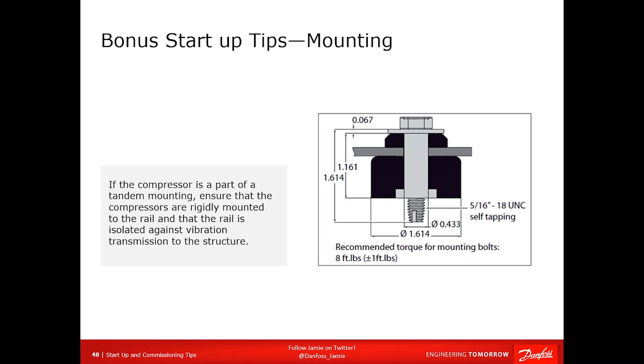This absolutely means these compressors cannot move independently. They have to move together. So do not float the compressors. Firmly attach the compressors to the rail, then float the rail on these rubber grommets to reduce vibration. But the compressors absolutely can't move independently.